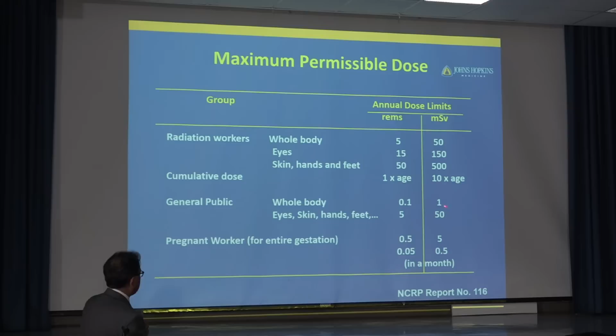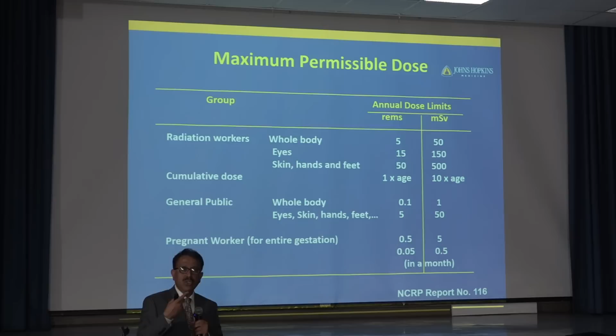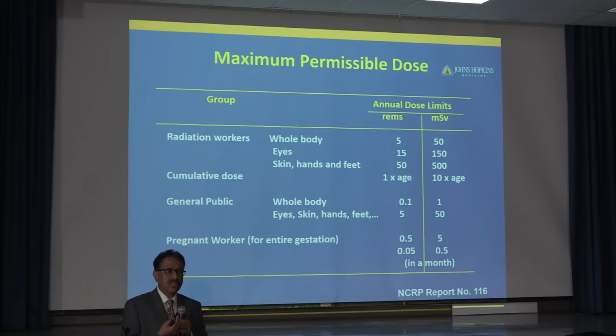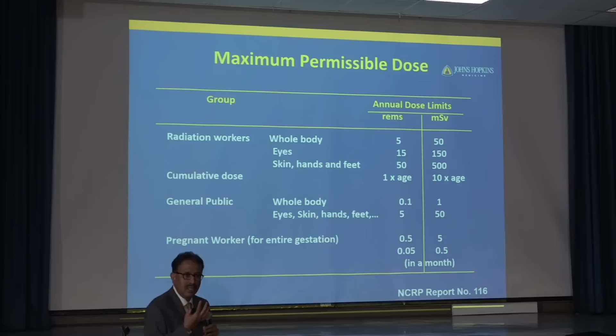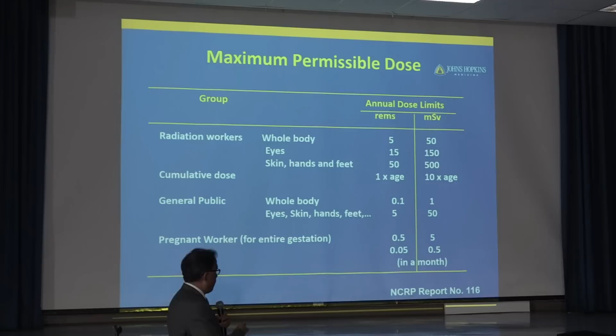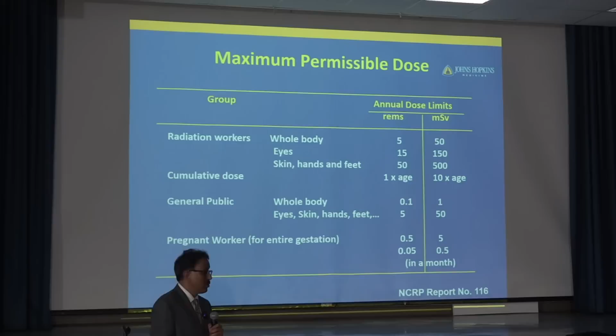And this is the limit for the general public, about 1 millisievert, and this is what we use for designing the X-ray room. If a member of the general public is standing outside, let's say there is an office space with administrators sitting next to each other for 24 hours, we can calculate and tell what the wall thickness has to be. Then, as you can see here, the eyes, skin and hands are given larger allowances because they have less sensitive organs, so the limits allowed are much higher. That's why for the hands you can just wear a ring badge and compare to the annual limit allowed. So pretty much you can answer the question yourself.